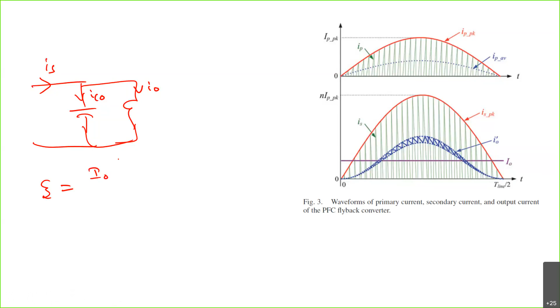Therefore you can define this zeta, the attenuation ratio of the current harmonics, as the ratio with I naught. If you calculate this, it is 1 by j omega C naught divided by 1 by j omega C naught plus j omega L naught. So it is 1 by 1 minus omega square L naught into C naught. So this is the zeta, the attenuation rate for high frequency harmonics. This is how to design L naught and C naught.